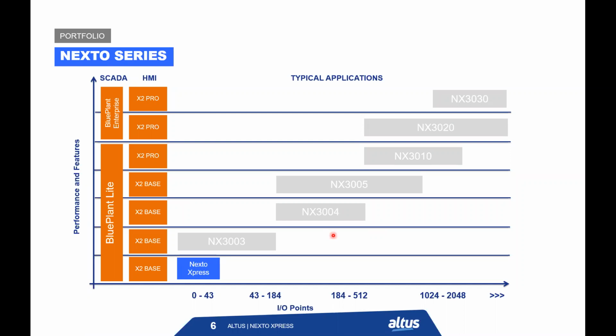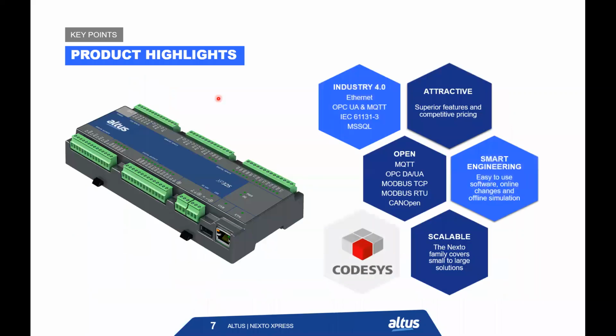So here we have some key points that I want to talk a little bit about. We call this Industry 4.0 ready because we have Ethernet, OPC UA, MQTT, and the IEC 61131 is presented here. Super features and competitive pricing, it's very important. Very open because we have MQTT, OPC DA, OPC UA, Modbus TCP, Modbus RTU, and CANopen.